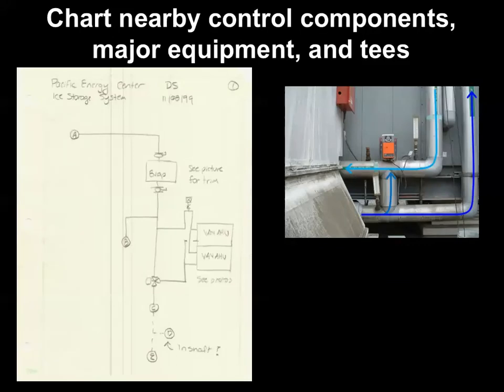Next, track piping or ductwork distribution to and from that equipment and make sure to capture things like control valve and damper arrangements, other equipment or load devices, and tees or branches. Elbows and other fittings may be important from a pressure standpoint, but for system diagram purposes, unless there's a special reason to represent them, only fittings that represent the order of connection between components are typically shown.